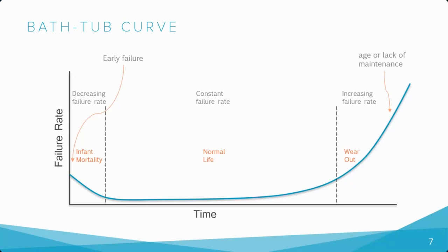Common causes of asset failure at this stage include manufacturing defects, installation errors, insufficient components, design flaws, and incorrect startup process. So, what can we do to minimize asset failure during the infant mortality period? Run acceptance and reliability tests to reevaluate equipment and check replaced parts of an asset. We can also run these tests every time we change design, process, or tools.